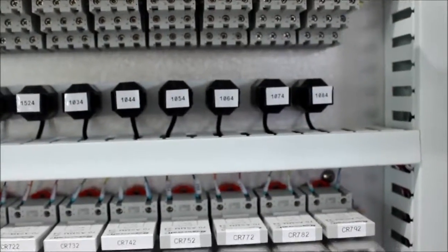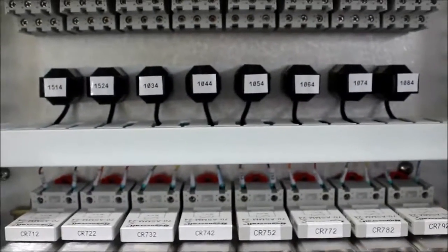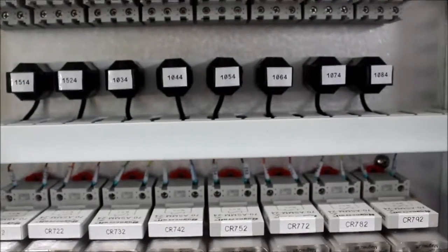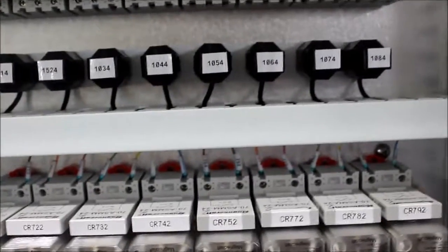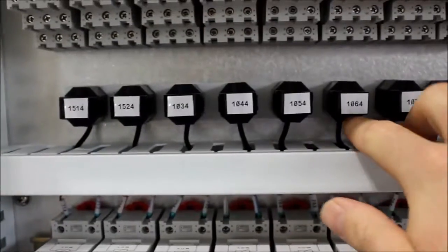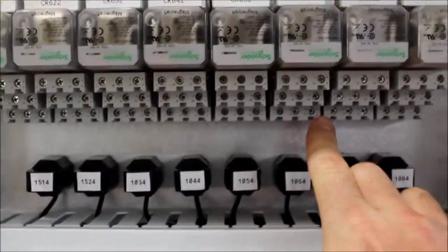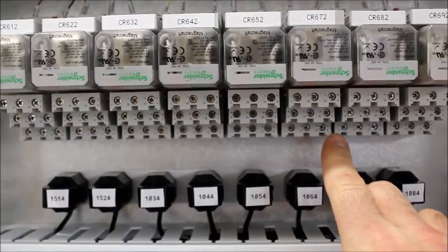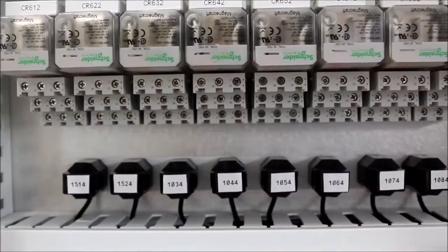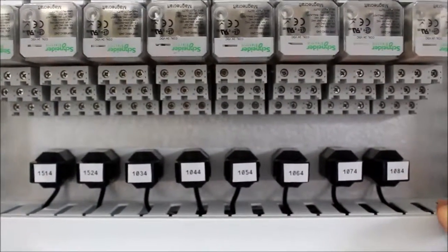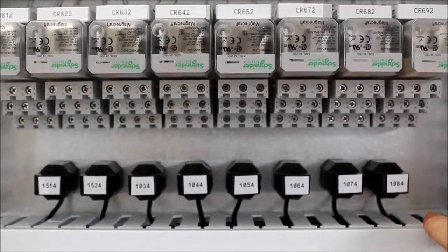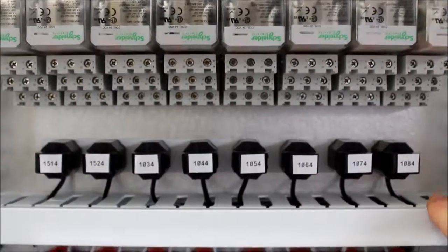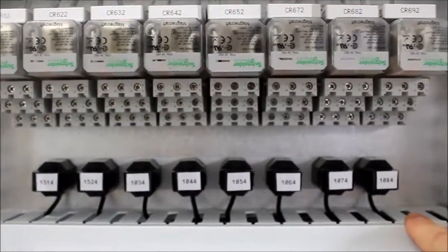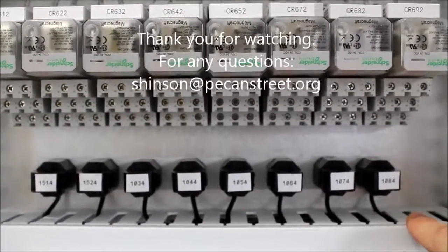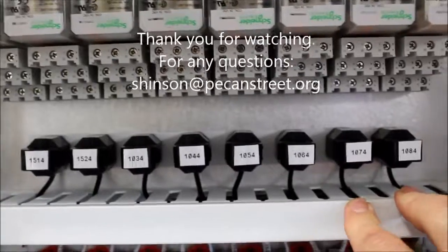In an installation, the output of the residential circuit breaker will be brought into the cabinet through the CT into the control relay, back out of the cabinet, and then continuing on to the residential structure branch circuits. And that way we can make use of the existing distribution panel in the residential structure and still have monitoring and control by the energy switch.